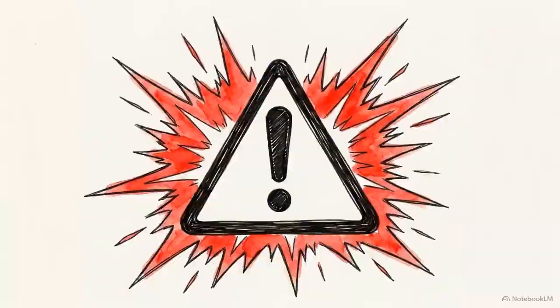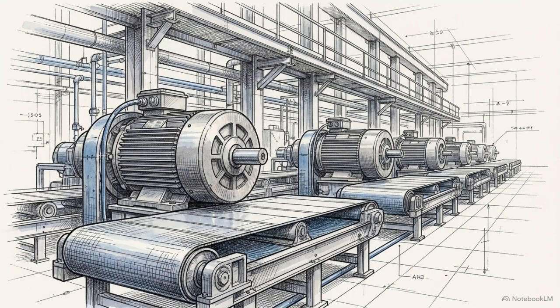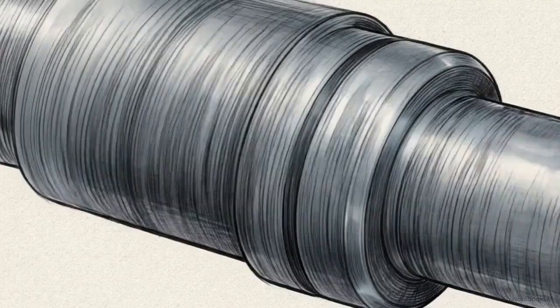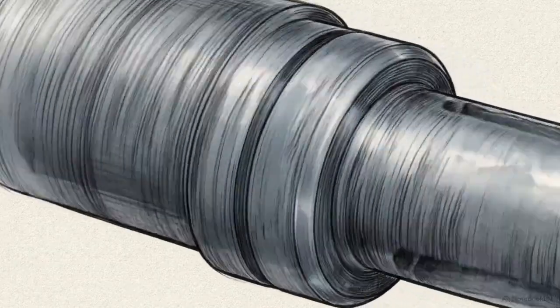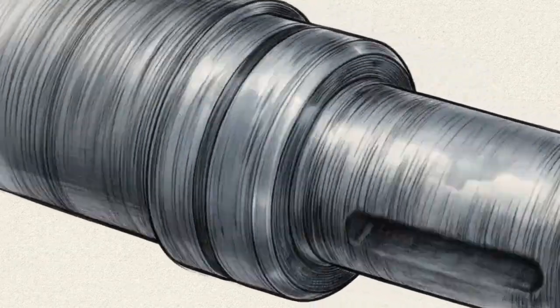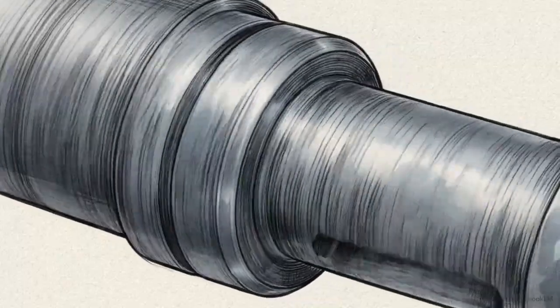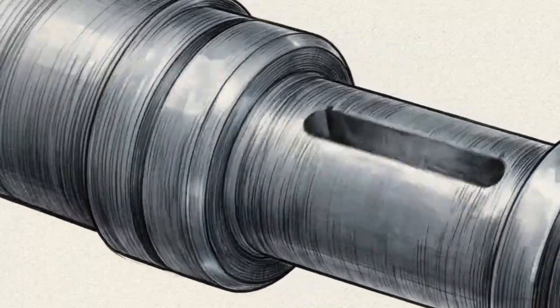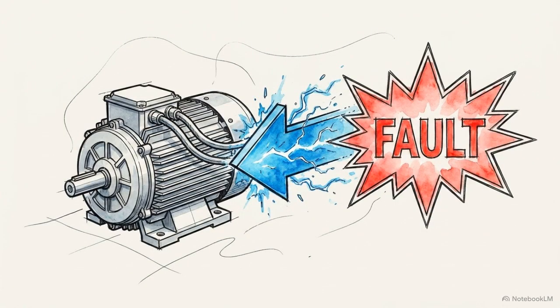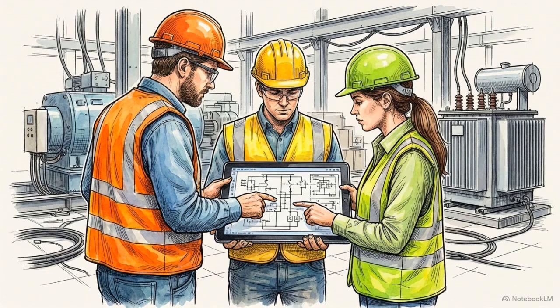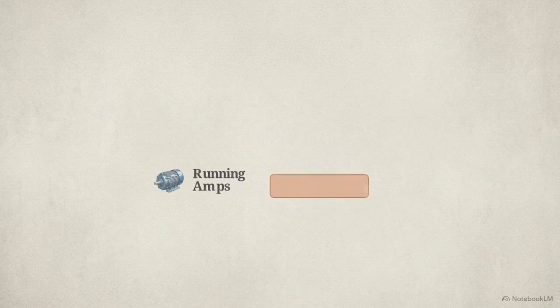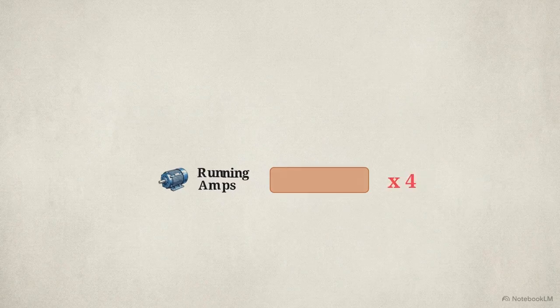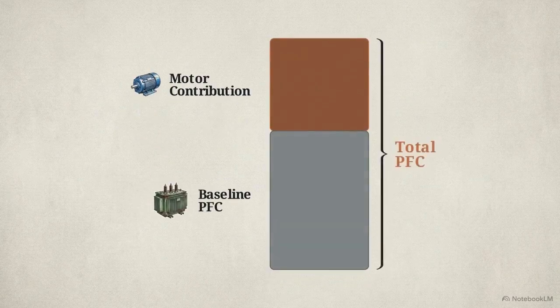The transformer is the primary engine of a short circuit, but there is a critical secondary variable often missing from baseline estimates: large industrial inductive loads. Heavy electrical machinery inherently carries massive physical inertia. When a short circuit occurs, facility voltage plummets, and these spinning motors instantly become generators, dumping their remaining kinetic energy backward into the fault. To account for this in the system architecture, engineers apply a strict multiplier. Calculate the total running motor load in amps, multiply it by 4, and add it directly to the baseline PFC.